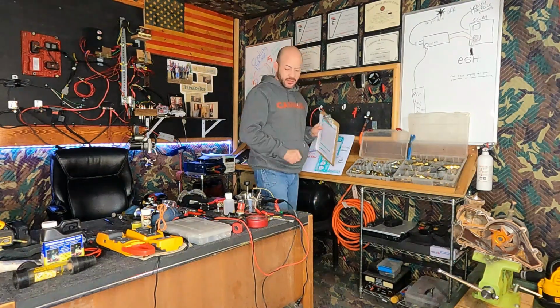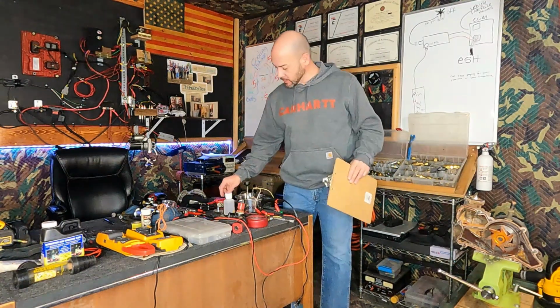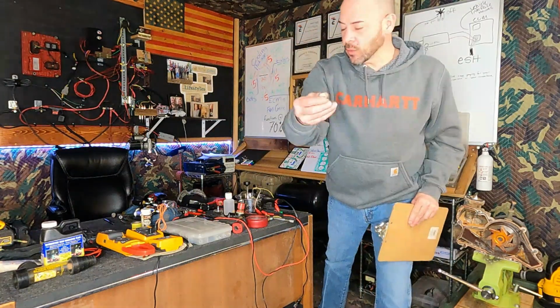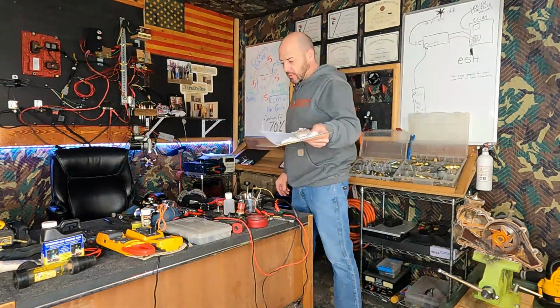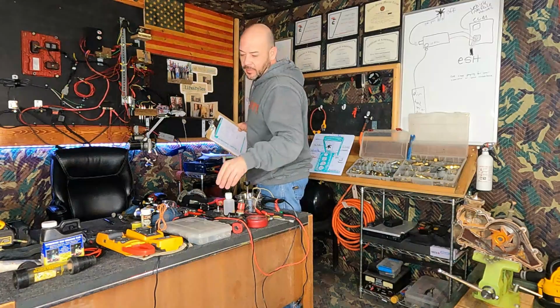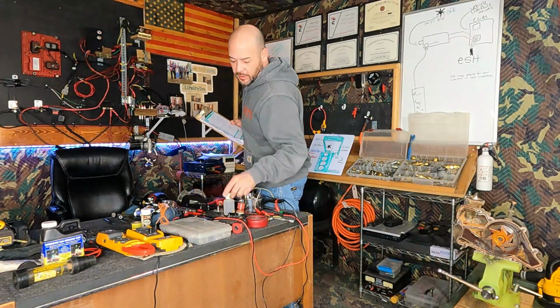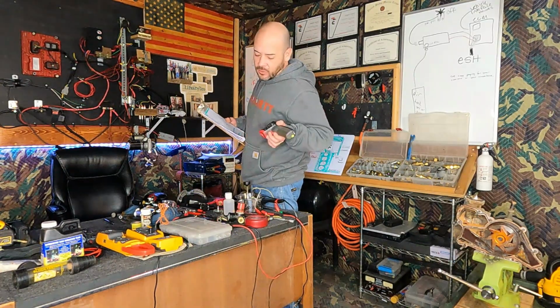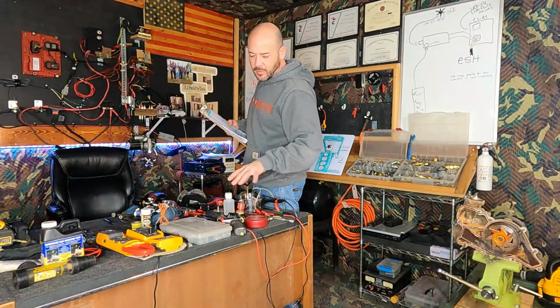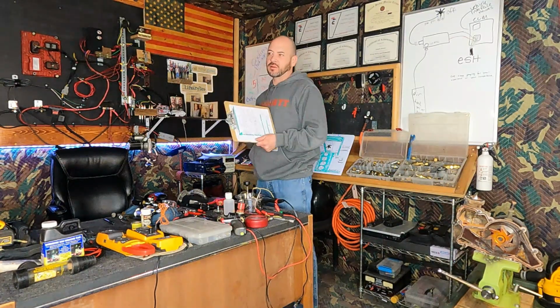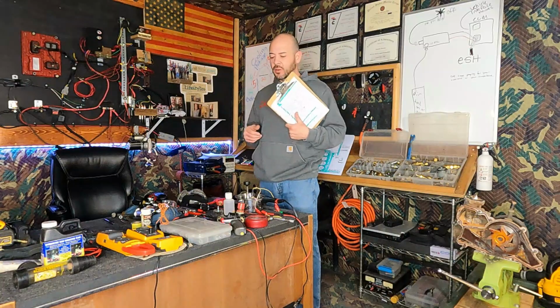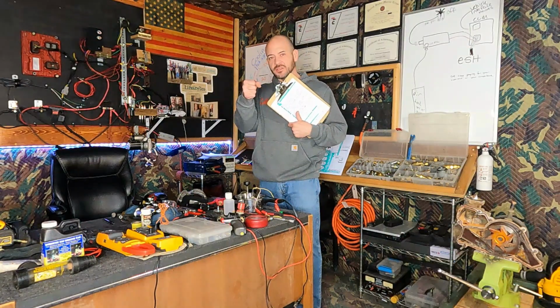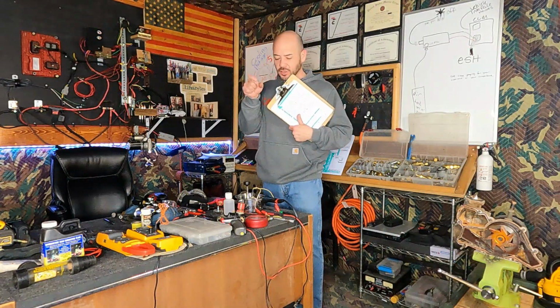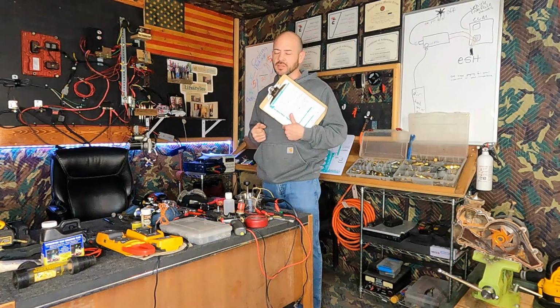So we got temp sensor. Here's a temp sensor right here. Here's another one. All right, the wires and the pins. I told you we have to make sure that that's a verified accurate measurement. So we take a thermal probe or a thermal gun, and we measure right next to the sensor. There may be a few degrees of difference. Make sure you're not doing it with air from a fan on. We want to do it in stale air, as static as air as we can. And it's a pretty accurate reading if you go close to the temp sensor.